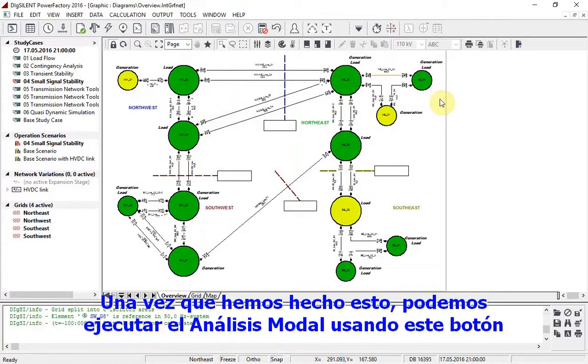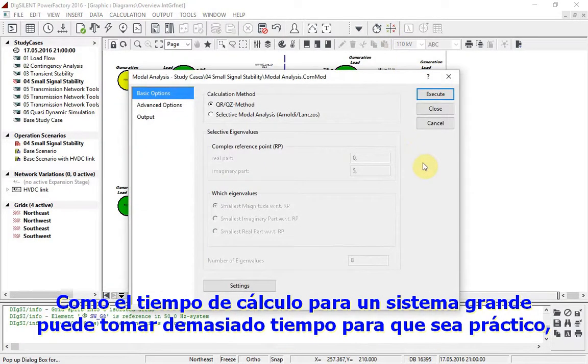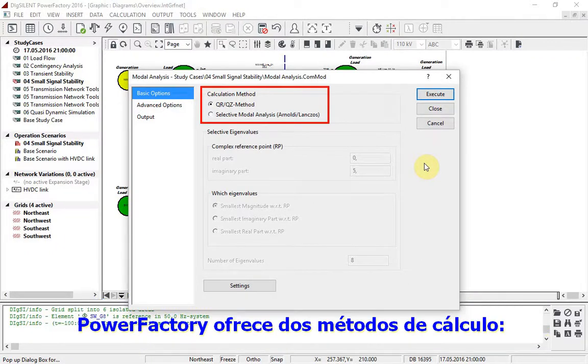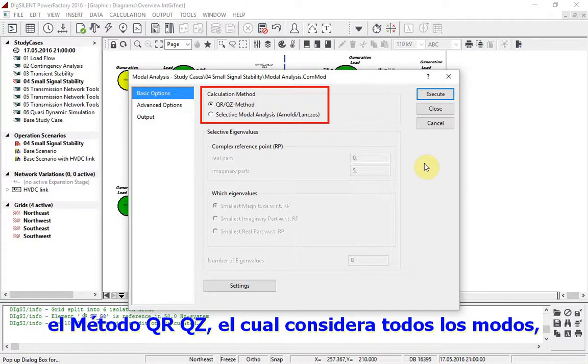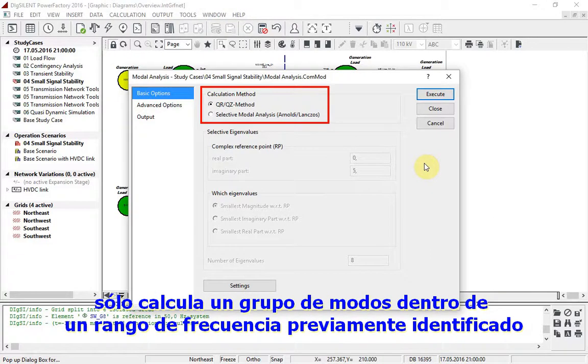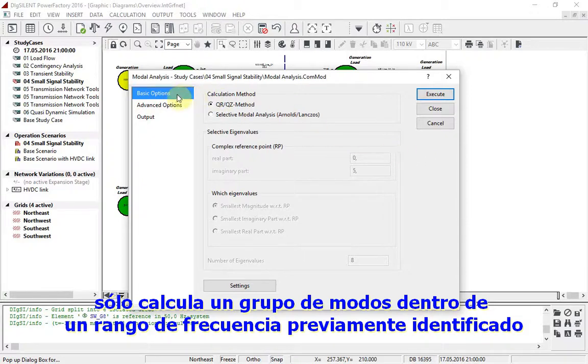Once this is done, we can run the modal analysis using this button. As the computation time for a large system can be too time consuming to be practical, PowerFactory offers two computation methods: the QRQZ method, which considers all modes, and the selective modal analysis method, which reduces computation time by calculating only a number of modes within a previously identified frequency range.